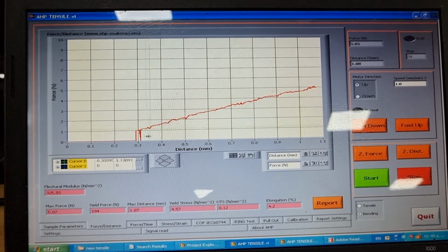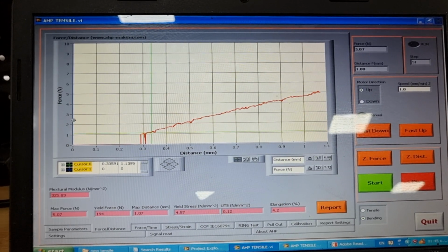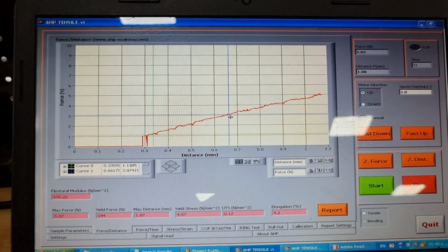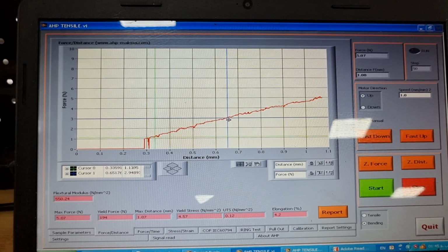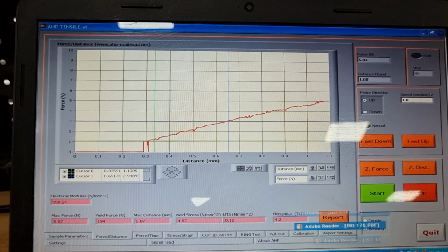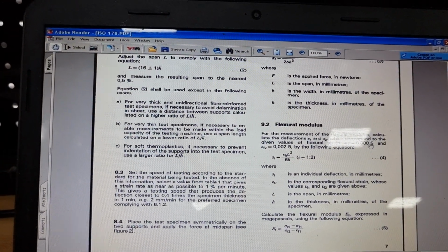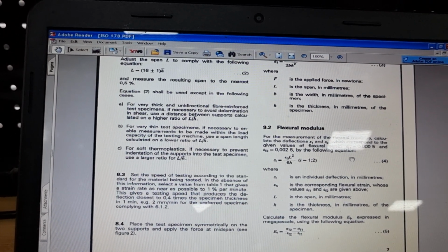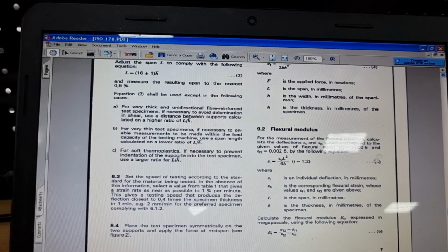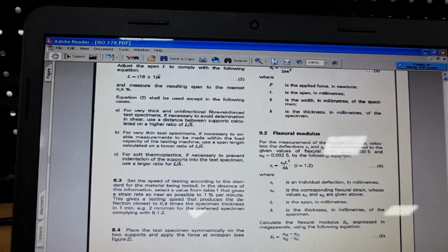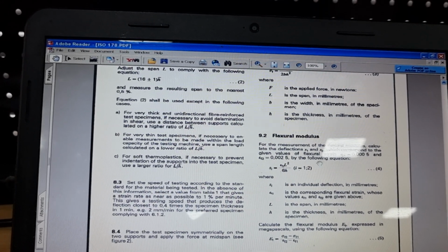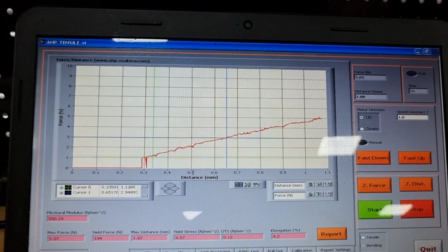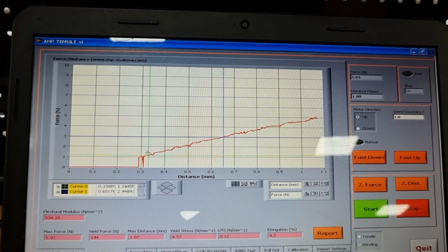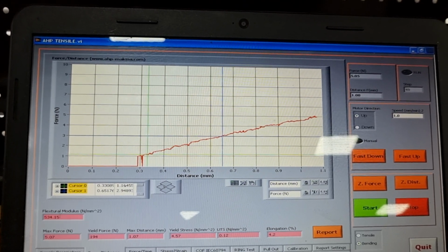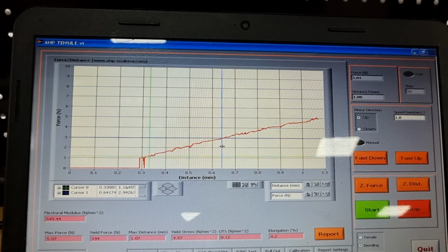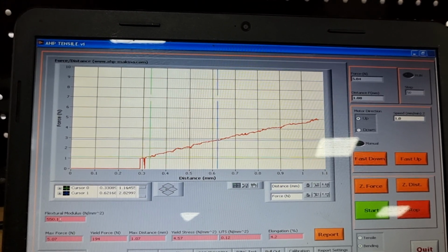This is the first cursor. I'm putting it here at a low displacement value. And here the second cursor, I'm putting it at, for example, 65. Suppose that the two displacement values related to the flexural strains are defined in the standard ISO 178. Suppose that the displacements related to these two values of the flexural strain are these values. I'm putting the cursors here, and it calculates the flexural modulus. You see the flexural modulus here.